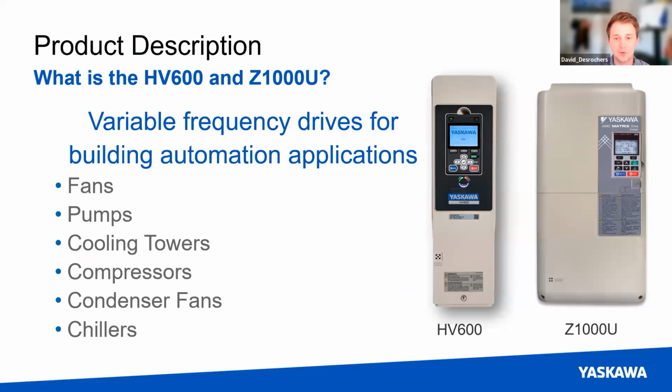Product description. So we got the HV600 over here on the left, and then the Z1000U on the far right. And so these VFDs are variable frequency drives used for a variety of building automation applications. And generally, you're going to be running those on variable torque loads like fans, water pumps in your cooling towers, compressors, condenser fans, and chillers.